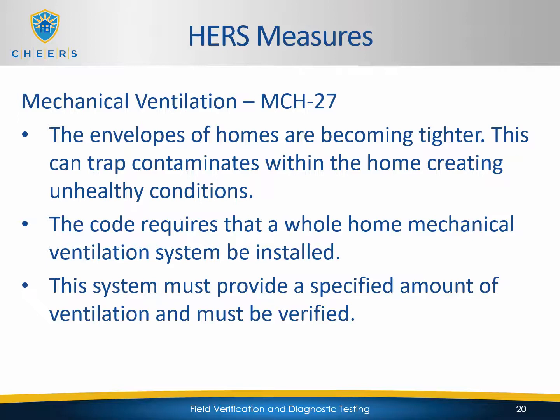In this particular test, we're going to measure those systems to ensure that the amount of air movement that is required is achieved. That value is going to be on the CF1Rs. You're just going to measure it and make sure that it's equal to or better than the value that's required.